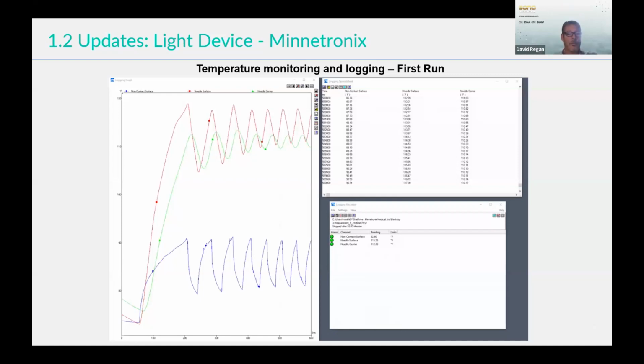This is an example of maintaining temperature, showing readings from three different thermocouples. That sawtooth curve holds temperature around the target. This was the very first time we did it with this new device, and it's only gotten better since. We're at the target temperature plus or minus about 3 degrees Celsius, well within the range we want, not getting anywhere close to ablation temperature. This will keep improving.